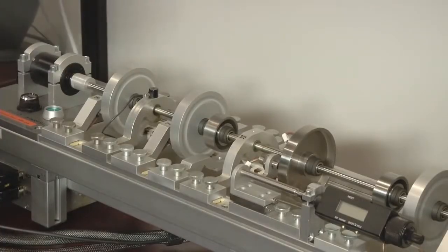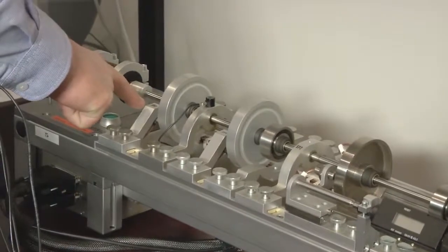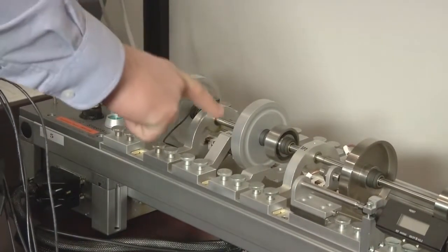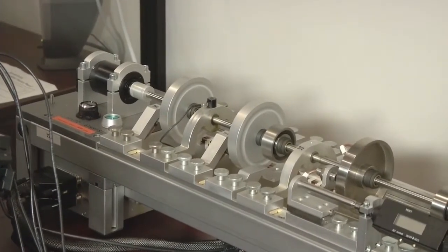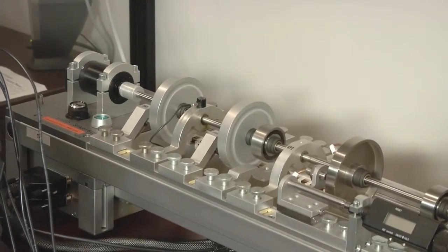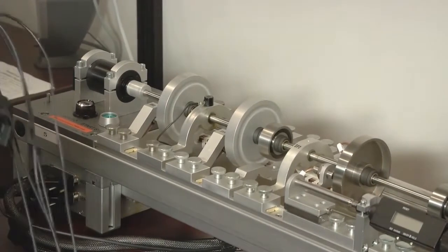So the CSI 2140 is now receiving live signals from these two displacement sensors, measuring the shaft at this location and this location to produce two live orbits, orbit plots. And the shape of those orbits can then tell us diagnostic information about the health of this sleeve bearing rotor here.